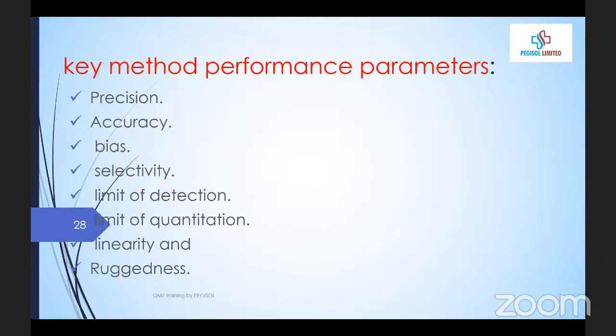Limit of detection: what is the limit of that detection? Let's say, for example, a malaria kit. Most of us, when we buy this reagent, don't look at the package insert. Look at the PI, read it. It will tell you that this malaria kit can only detect when the parasite count is up to 1,000 per microlitre of blood. So once the parasite count is less than that, that test kit cannot measure it. That's one limit of detection. We have linearity of the equipment. Even for quantitative tests, with some reagents, once the value is less than maybe 20, it cannot analyze it. Let's say, for example, some PSA, once it's above maybe 2,000, it cannot detect it. You have to start doing dilution. So that shows you the limit of detection. We have linearity and ruggedness.